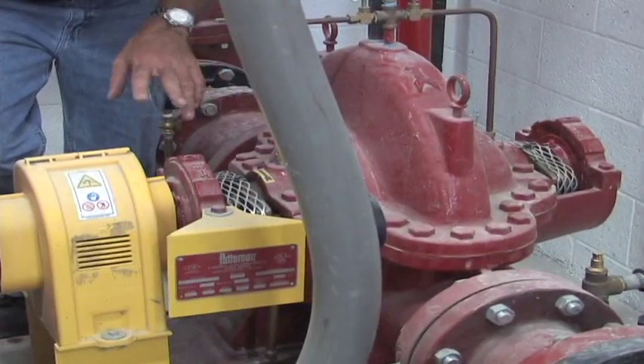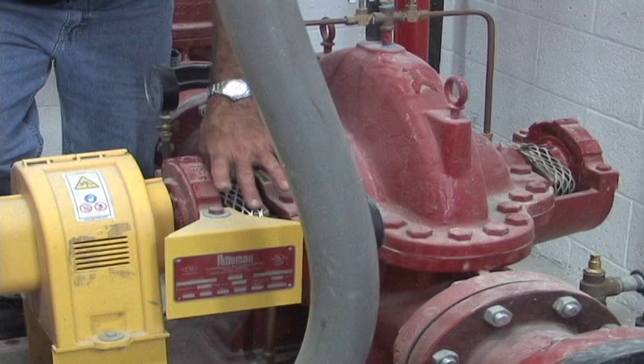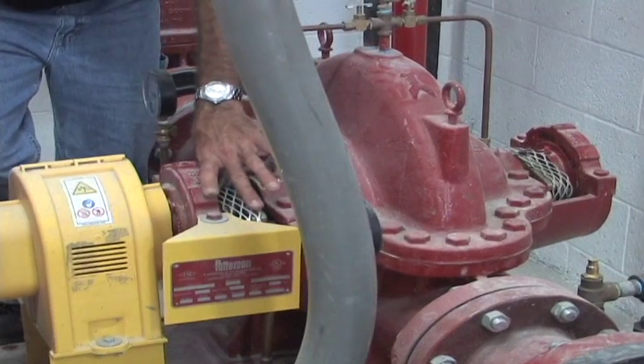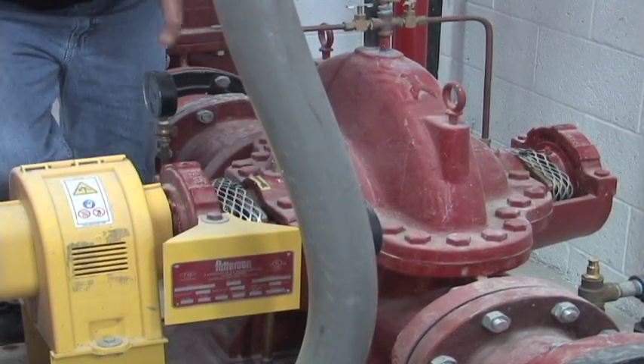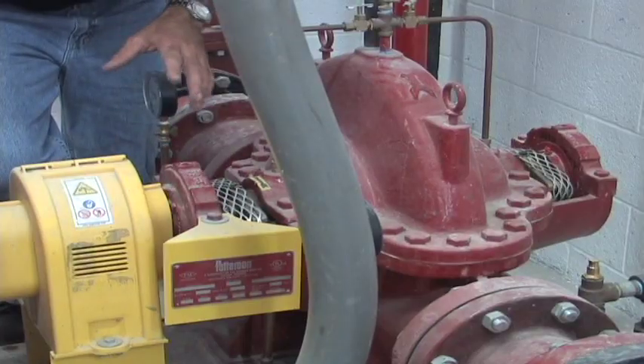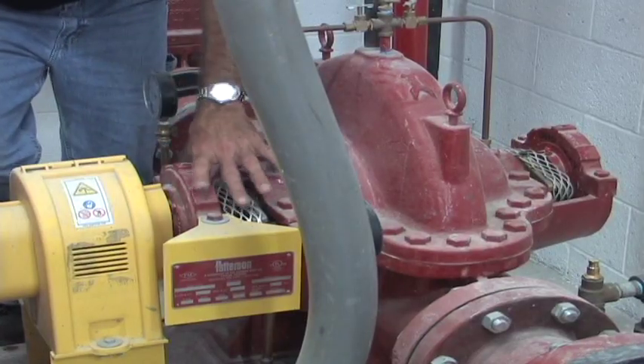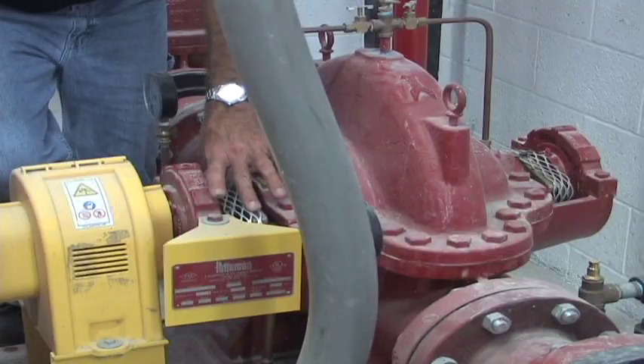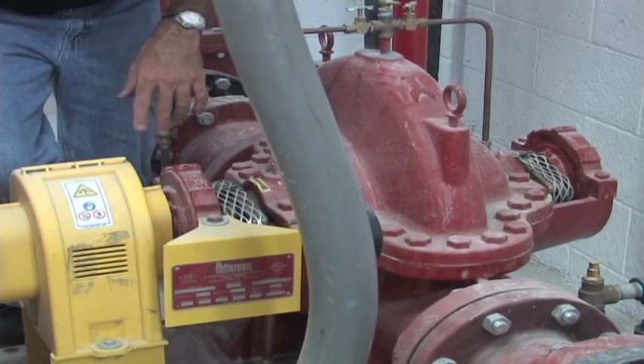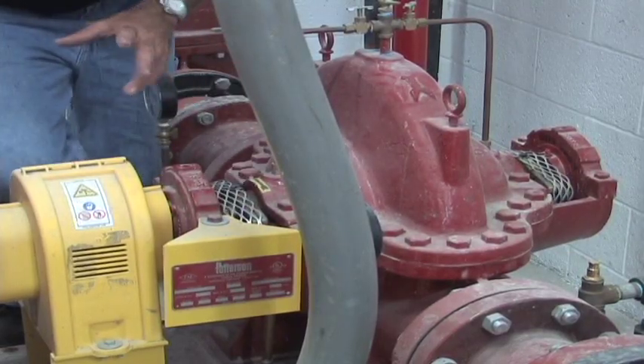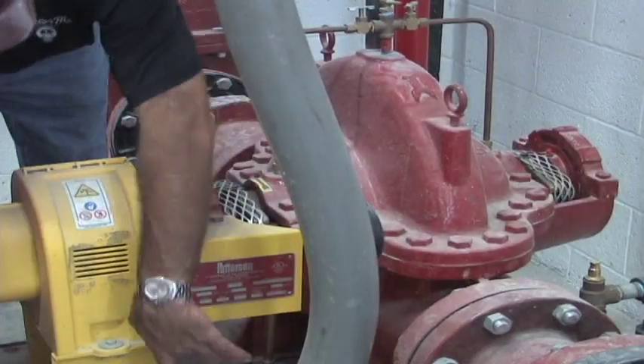It's natural for somebody to come in here and take the swing bolts and tighten these packings down to where they get tight. And then during the operation of the pump, you start to have smoke, a little steam coming out from the packings. You want to keep this thing dripping, like I said, 1 drip per second.